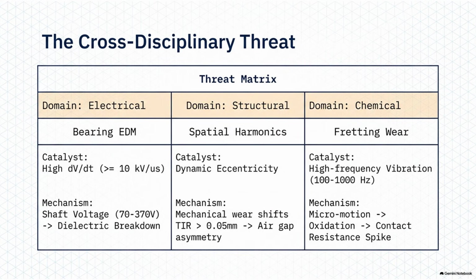It absolutely does. When you shift voltage that violently, you create what is known as parasitic capacitance. Okay, parasitic capacitance. What does that actually look like? Well, think of the inside of the motor. You have the stationary part, the stator, loaded with copper wire carrying this violently pulsing electricity, and sitting right inside it, separated by just a tiny air gap, is the spinning rotor. Even though they aren't physically touching, that pulsing magnetic field is so intense that the electricity essentially leaks across the air gap. Exactly. The rapidly changing voltage on the stator actually induces a sympathetic voltage on the rotor. It physically couples onto the solid steel motor shaft.